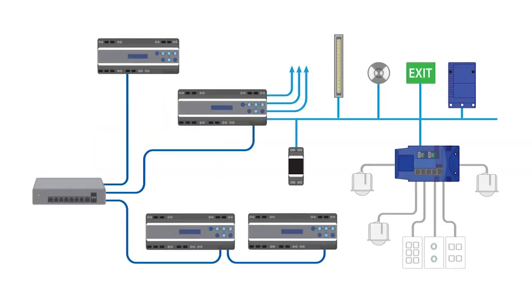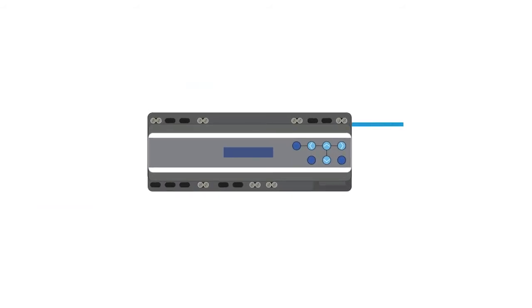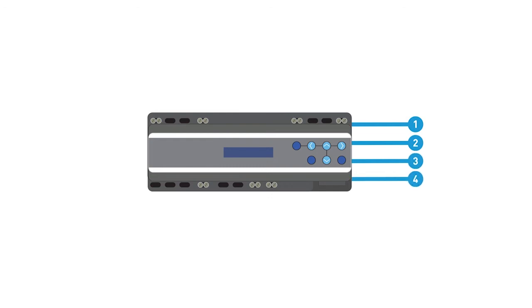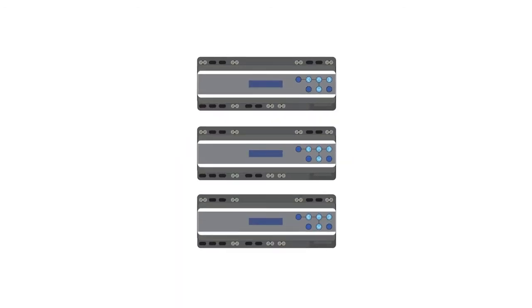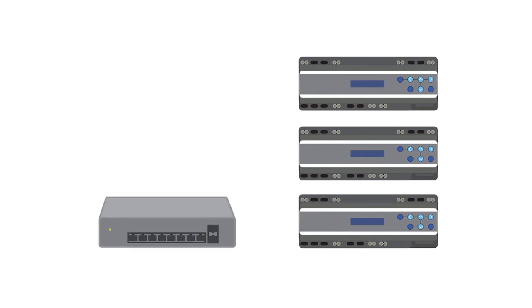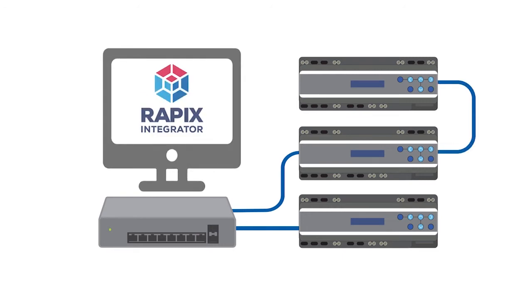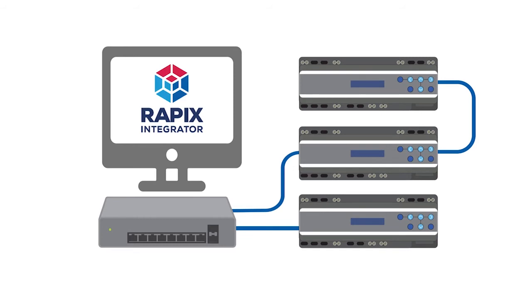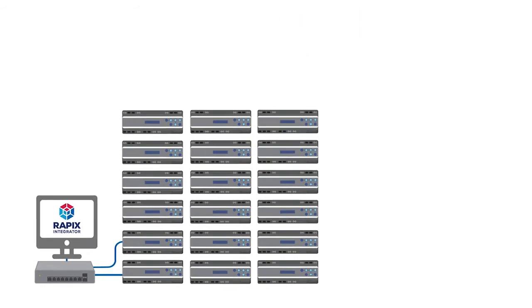At the heart of the Rapix lighting control system is the Rapix zone controller. Each zone controller is used to connect up to four DALI lines to the system. Multiple zone controllers are connected together using a standard Ethernet network. Each zone controller is connected to a standard Ethernet switch or daisy-chained together via built-in Ethernet ports. Rapix Integrator software, connected via a PC and Ethernet, can now be used to create the required control zones. The number of DALI zone controllers and lines connected is practically limitless.